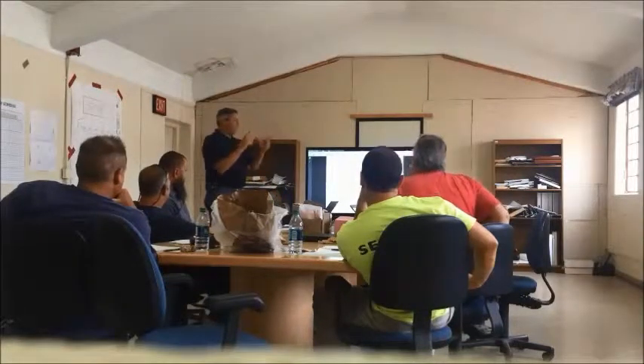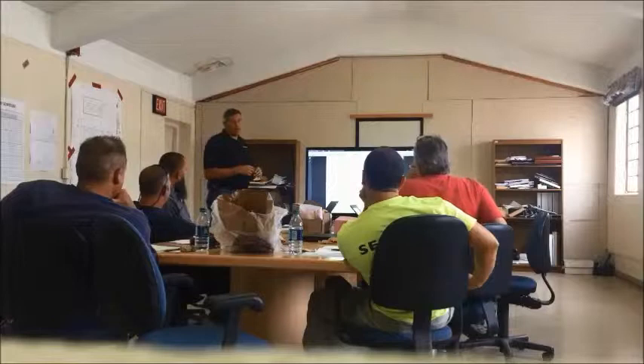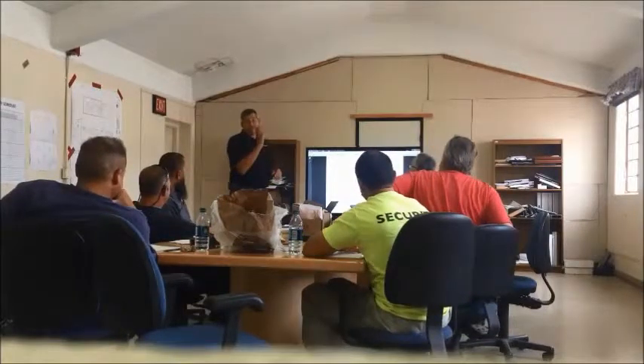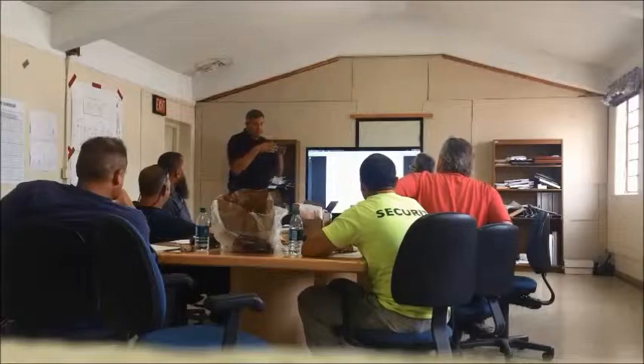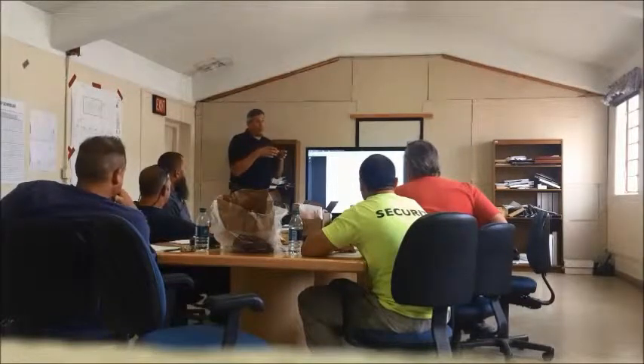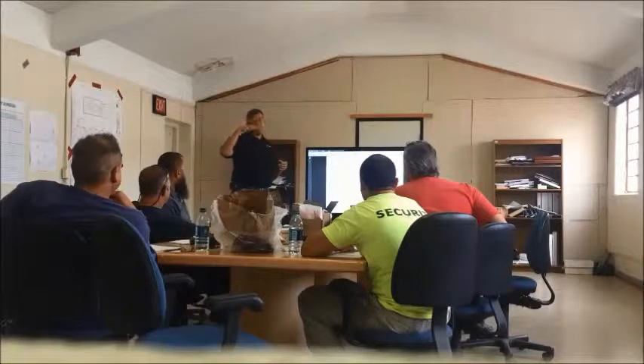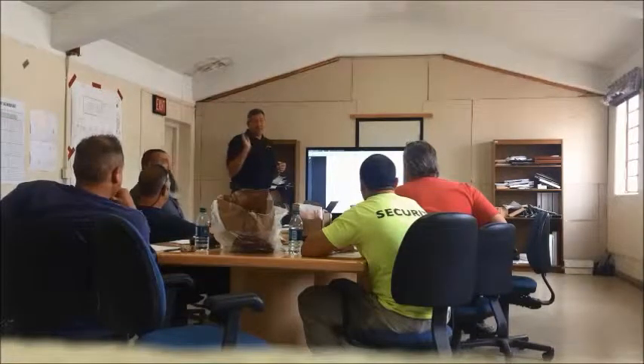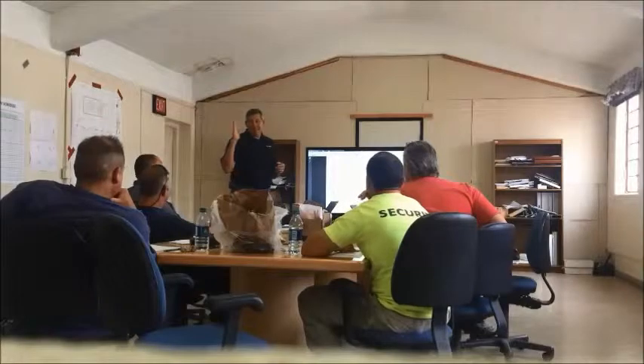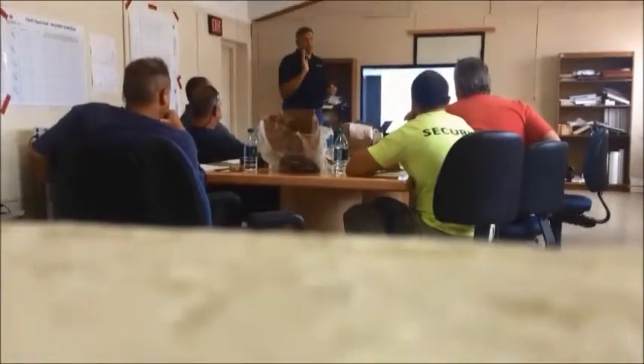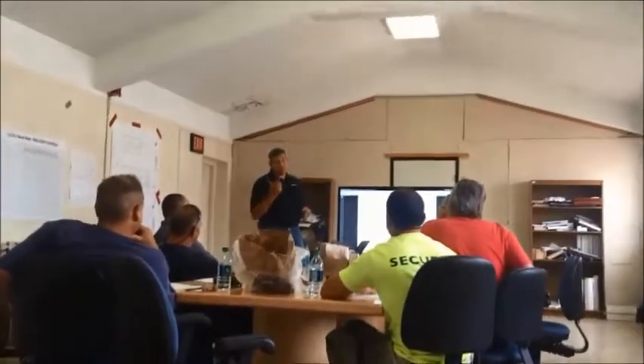But on this particular display, they have a monitoring display or HMI. It shows the vibration that's being emitted on that particular fan base at any given point in time. And what I did notice when we had certain wind conditions, they can move around a bit because the stacks are quite high, and you'll see the changes on the display. It's impressive how these transducers can respond based on movement. But they do all have a limit switch, so that in the software they'll trip and turn it down if it gets excessively aggressive with the vibration.